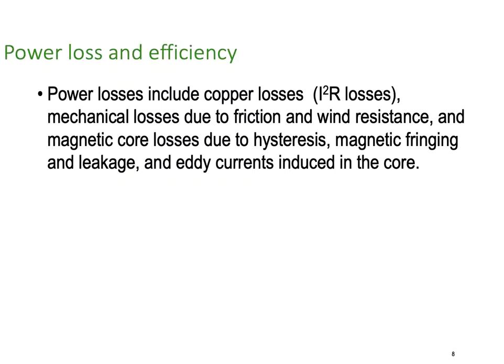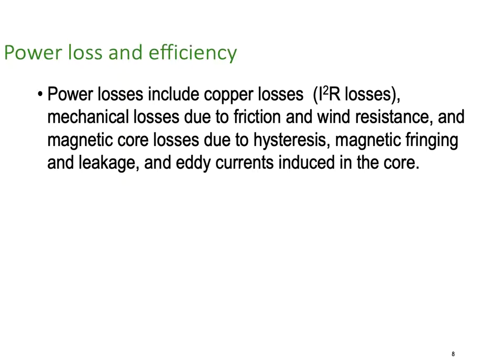Now for power loss and efficiency. Power losses include copper losses, the I²R losses around the machine, mechanical losses due to friction and wind resistance, and magnetic core losses due to hysteresis, magnetic fringing, leakage, and eddy currents in the core. Therefore, the prime mover driving a DC generator has to provide sufficient power to overcome all these losses - it has to put in more energy mechanically than it will get out electrically.